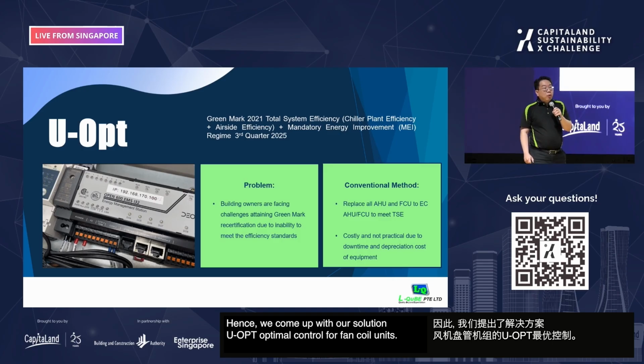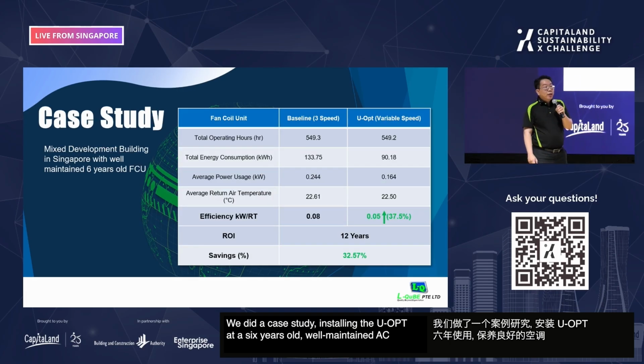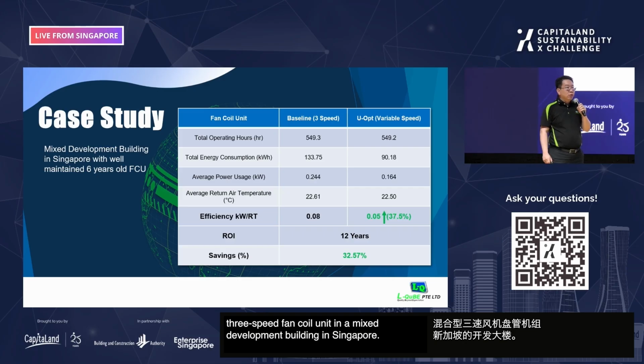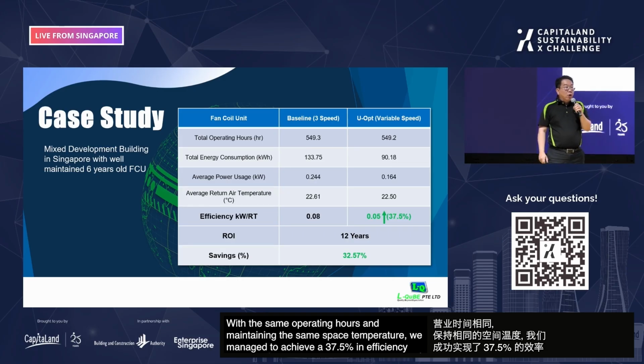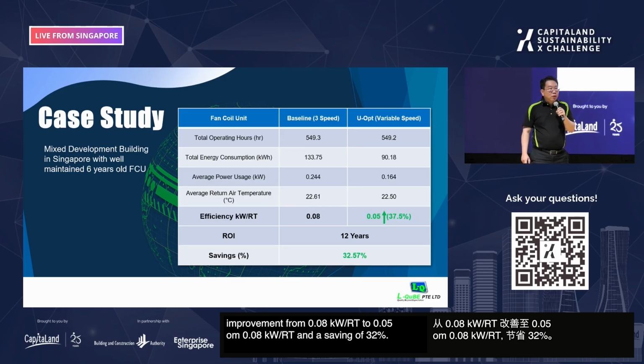Hence we came up with our solution, UOPT, Optimal Control for Fan Coil Units. We did a case study installing UOPT on a 6-year-old, well-maintained AC 3-speed fan coil unit in a mixed development building in Singapore. With the same operating hours and space temperature maintained, we achieved a 37.5% efficiency improvement from 0.08 kW per ton to 0.05 kW per ton, and a saving of 32%.